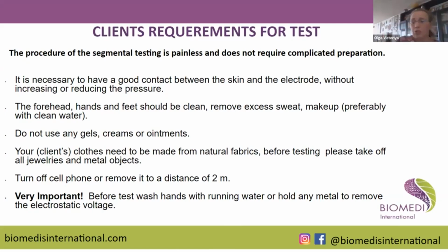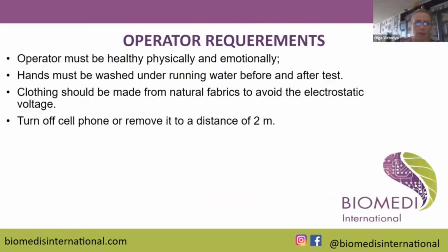And for the same reason, when we are going to use electrodes, try not to connect them together, one to another. One time I did it and I had to send my device for repair. It doesn't happen all the time, but please be careful. Tell your client not to click the electrodes together.